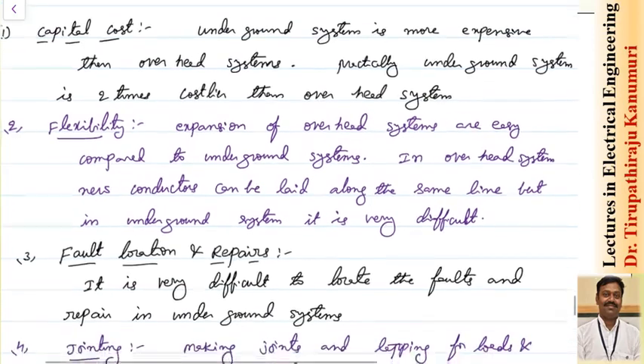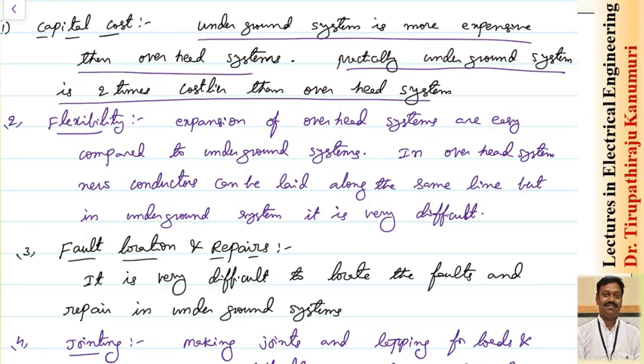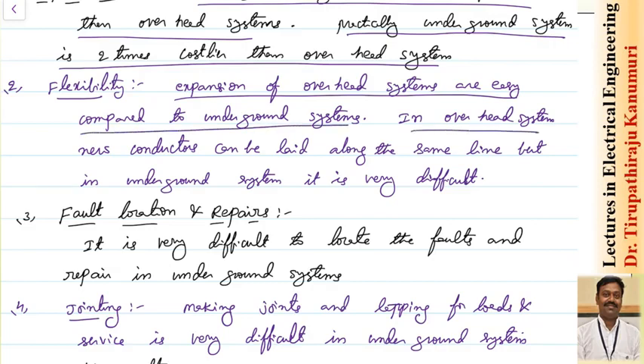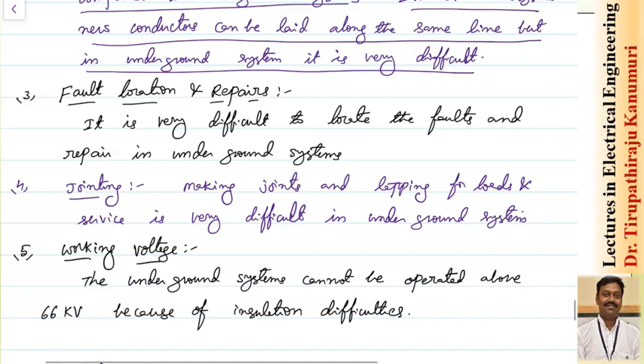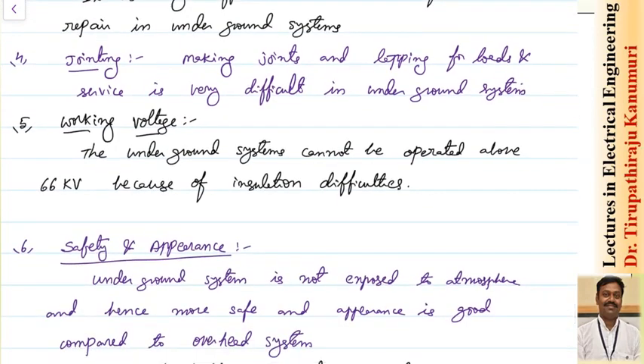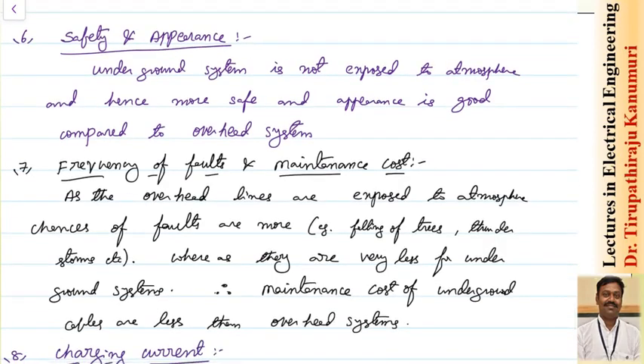Now the summary: First, capital cost — underground cables are more expensive than overhead systems; practically underground systems are two times costlier. Second, flexibility — expansion of overhead systems is easy; in overhead systems a new conductor can be laid along the same line, but in underground systems it is very difficult. Third, fault location and repairs are very difficult in underground systems. Tapping for load is also very difficult in underground systems, and underground systems cannot be used for voltages greater than 66 kV.